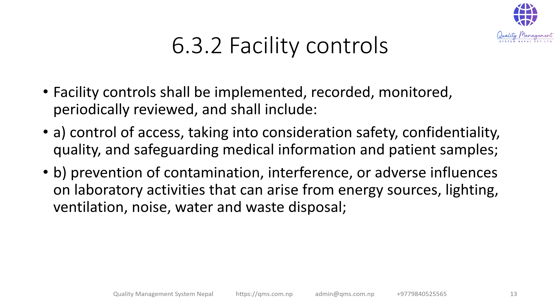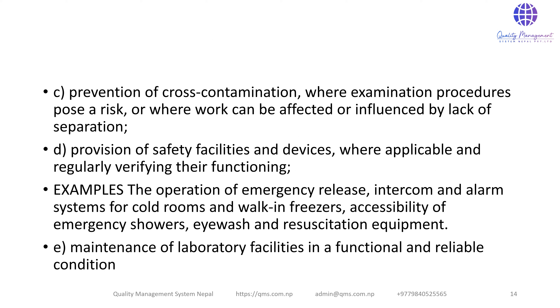6.3.2 Facility Controls: Facility controls shall be implemented, recorded, monitored, and periodically reviewed. These shall include: control of access taking into consideration safety, confidentiality, quality, and safeguarding of medical information and patient samples; prevention of contamination, interference, or adverse influences from energy sources, lighting, ventilation, noise, water, and waste disposal; prevention of cross-contamination where examination procedures pose a risk; provision of safety facilities and devices with regular verification of functioning, such as emergency release intercoms and alarm systems for cold rooms; and maintenance of laboratory facilities in a functional and reliable state.